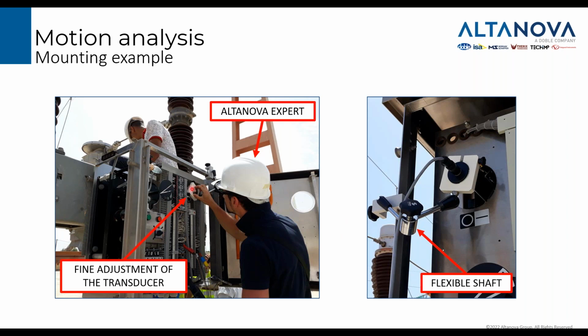The position of the transducer is very important. It must be done with high accuracy. If you make a mistake in the coupling, in the mounting, then your measurement will not be good. This is another example where it's possible to use a flexible shaft with magnets or with screws. So the concept is that for every circuit breaker, you must check what the mechanical layout is, and according to that you need to find the best mechanical solution to connect the transducer.